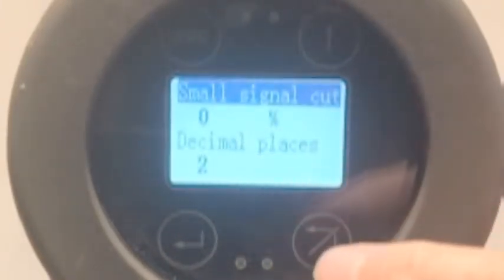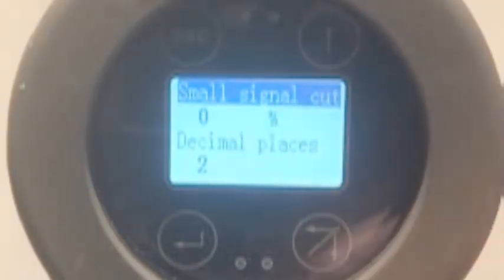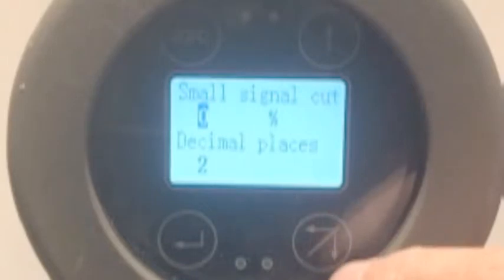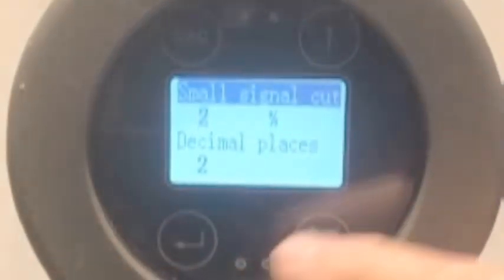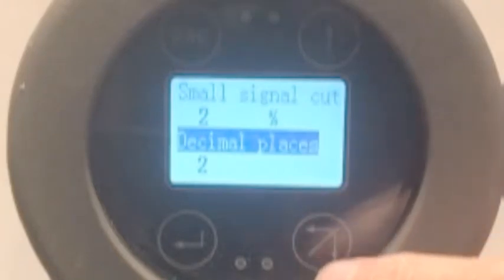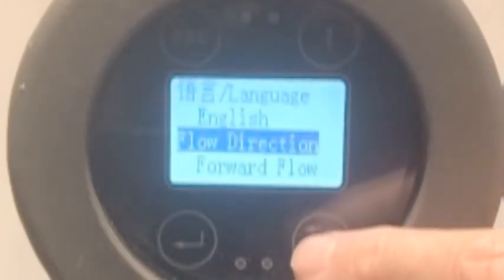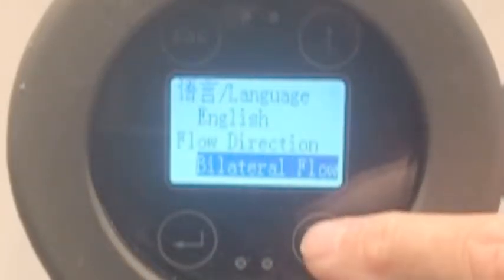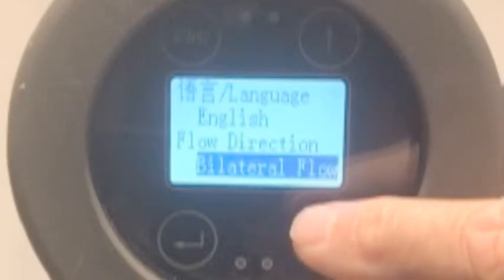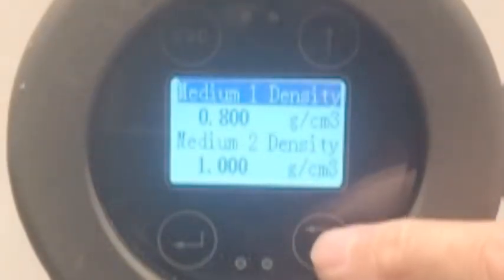Parity check: none. Small signal cut-off — this is where you set the 'if less than X' threshold. Let's set that one to 2%. Enter. The number of decimal places — obvious. And then we're back to flow direction. You can enter and choose forward, reverse, or bidirectional. Mostly people use forward flow. And there we go — that is it.